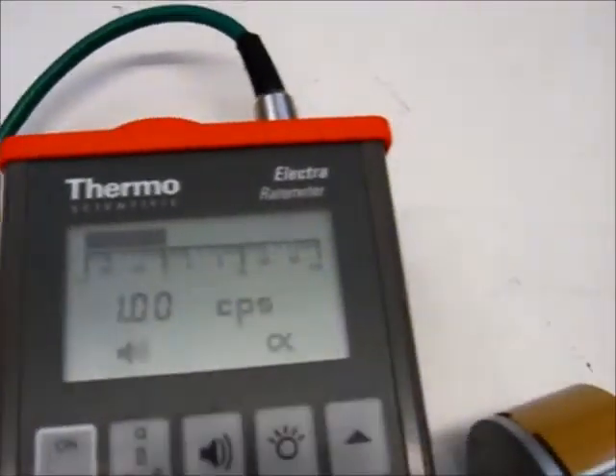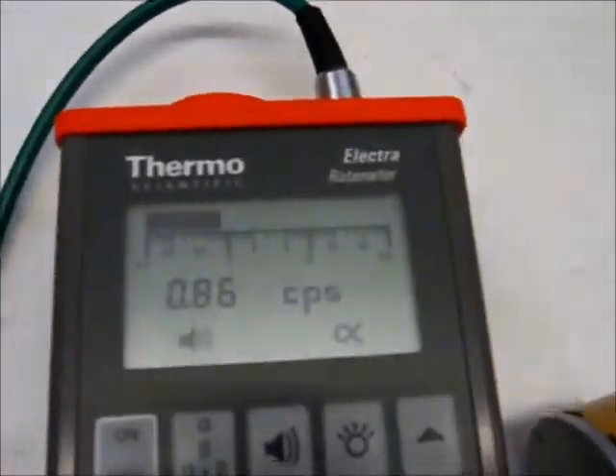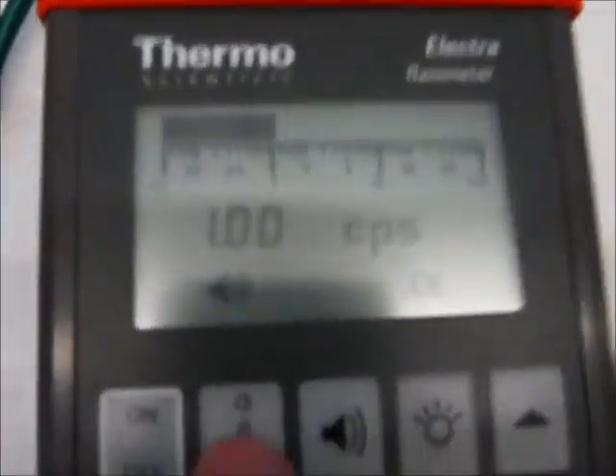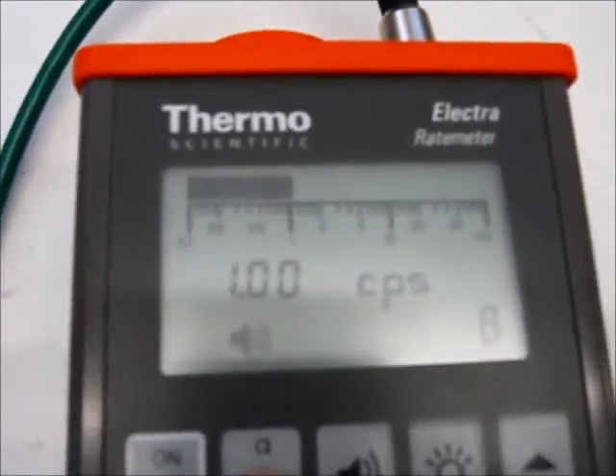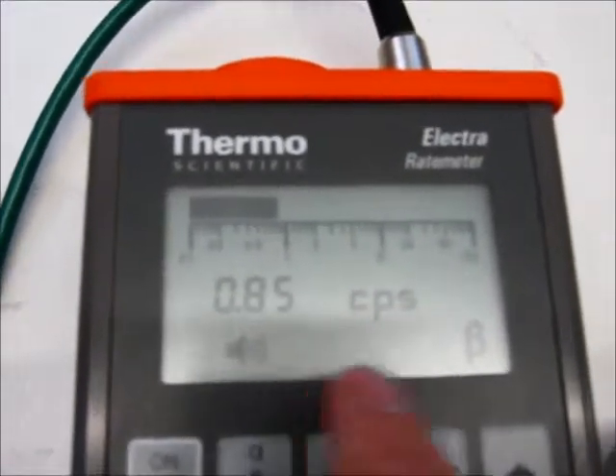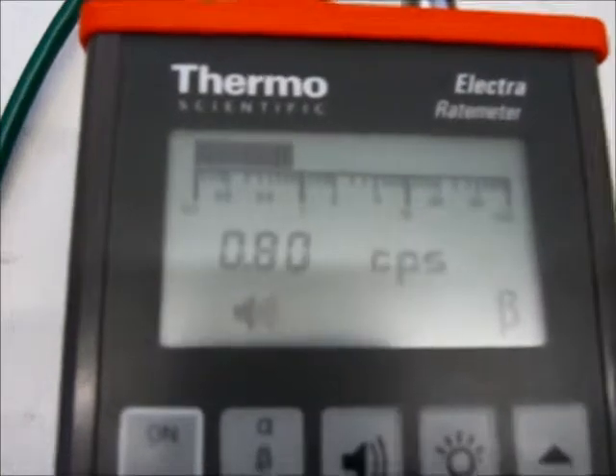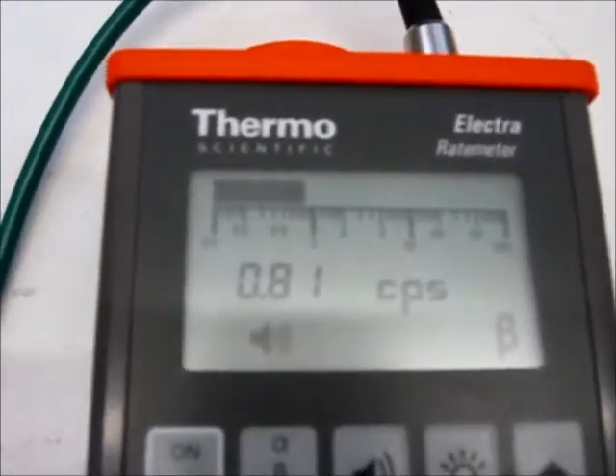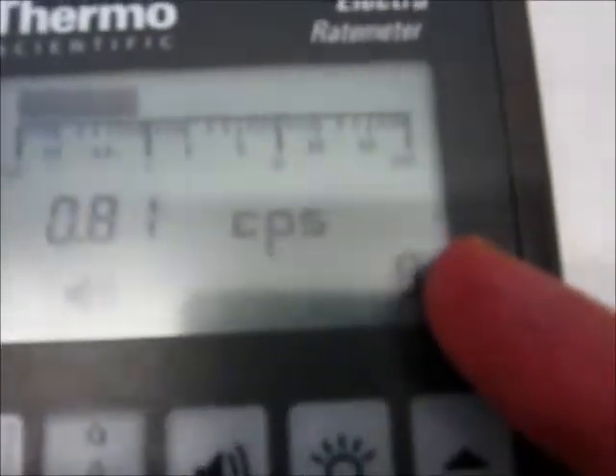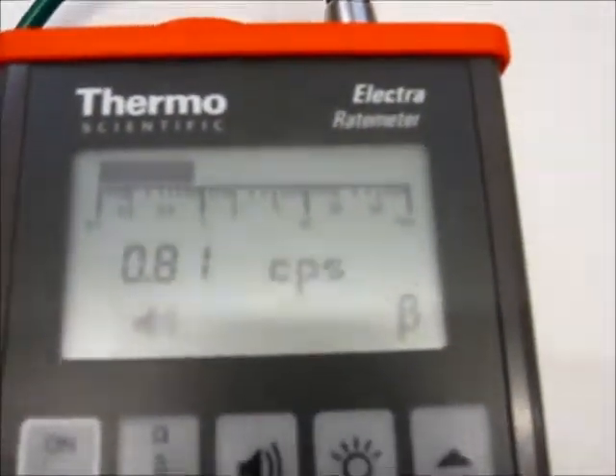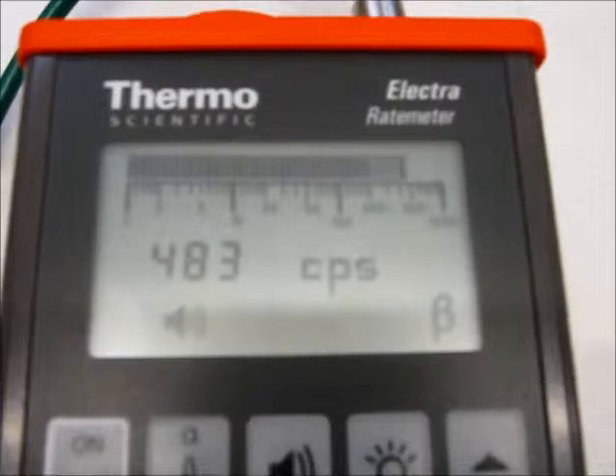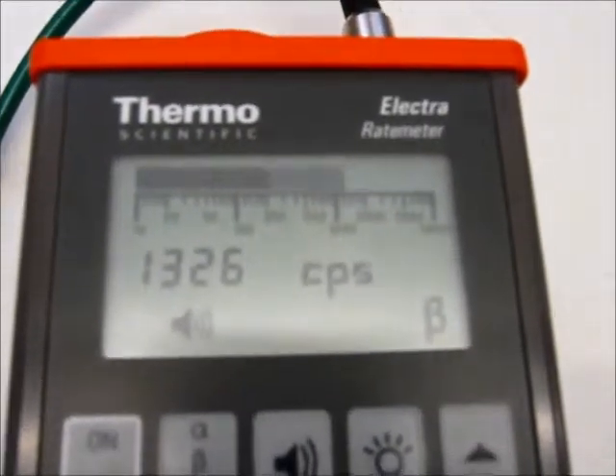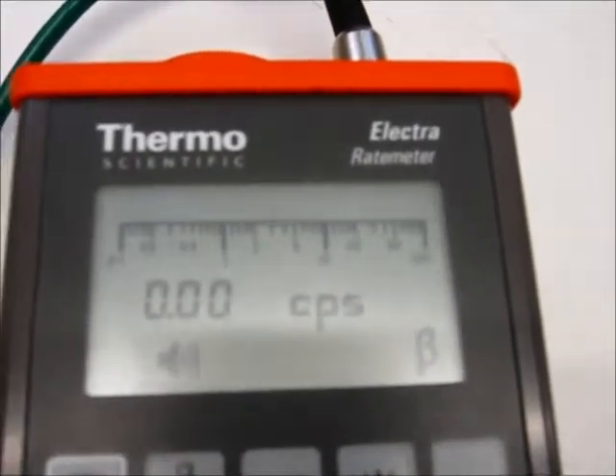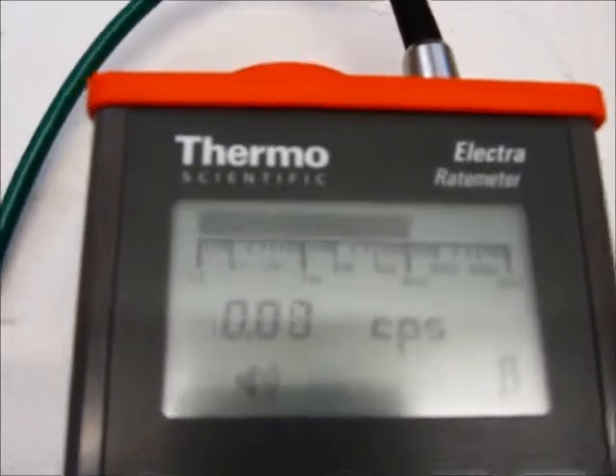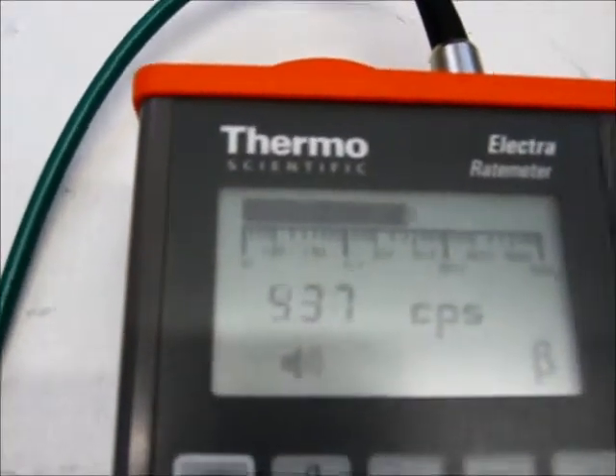You may also have seen the battery light flash up there. That doesn't mean that the battery is low. The system draws a lot of current, so sometimes the battery light will light up when you get a high signal. It's only if the battery light's consistently on that you would need to change them. So I've now changed the system to read betas, and if I monitor now, you'll notice a different change in tone to demonstrate beta contamination.